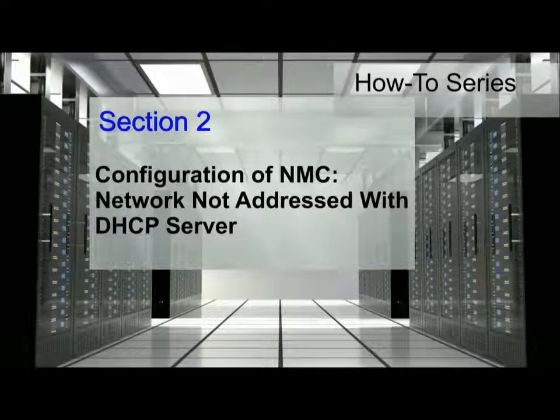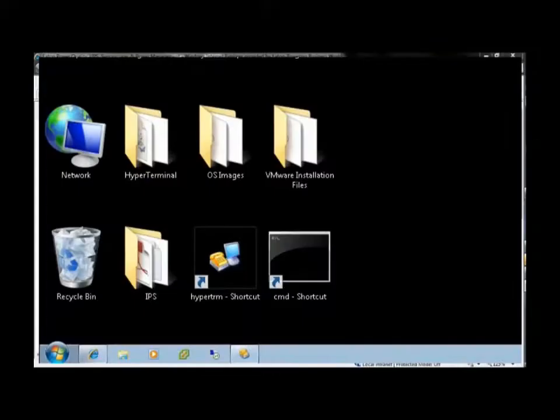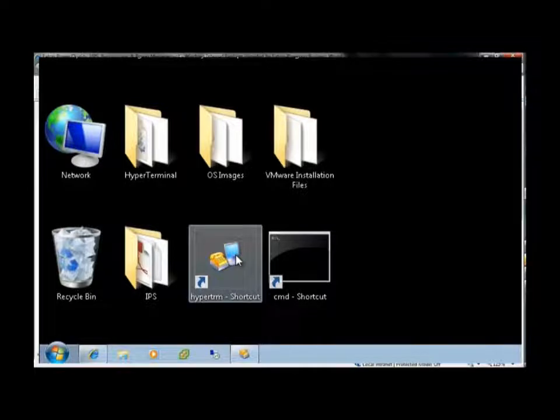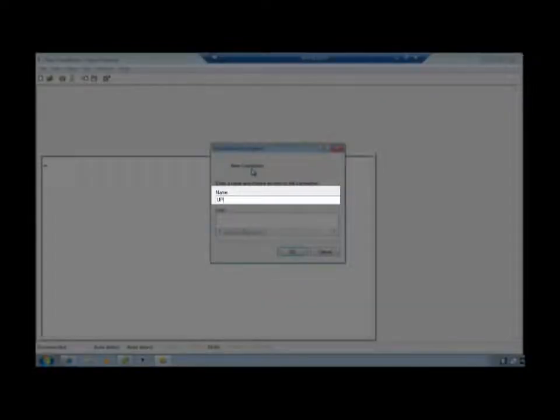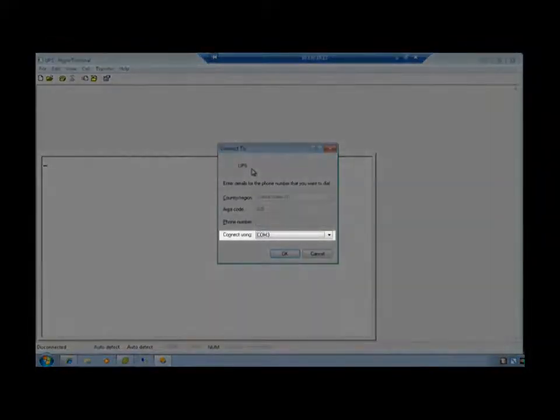Configuration of the network management card within an environment where the network is not addressed by a DHCP server. Once the physical connection is made, launch a hyperterminal type emulator to configure the serial connection to the card. Once launched, the connection description text box will appear. Enter the name desired for the UPS system and press OK. Using the Connect to text box, choose your designated COM port for your connection and select OK.